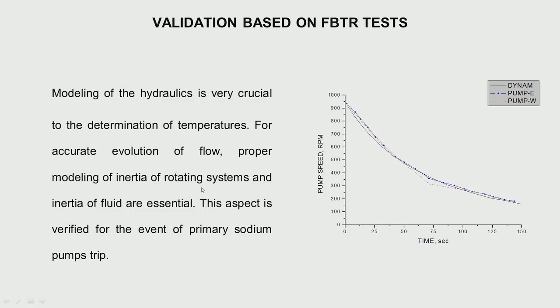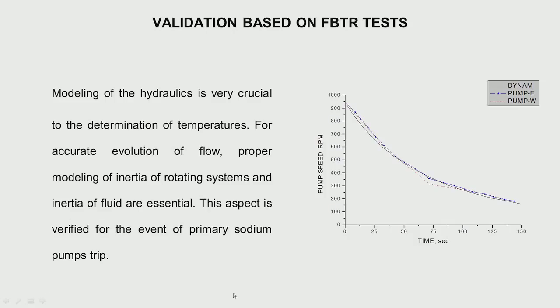When we started commissioning the FBTR reactor, we started comparing results with what we had from France, and then with data from FBTR itself. Looking at pump speed versus time — E means east loop, W means west loop, and DYNAM is our code — the predictions and actual findings are quite close. This means there is proper modeling of the inertia of the rotating systems and the inertia of the fluid. This again gave us confidence that our modeling is good — at every level when we develop confidence, we know we are close to reality.